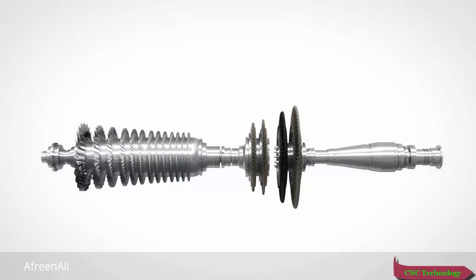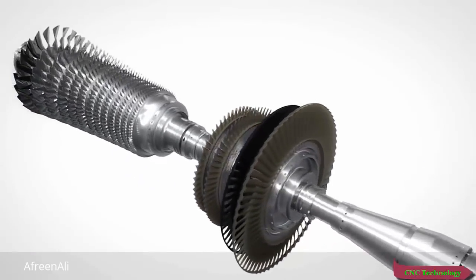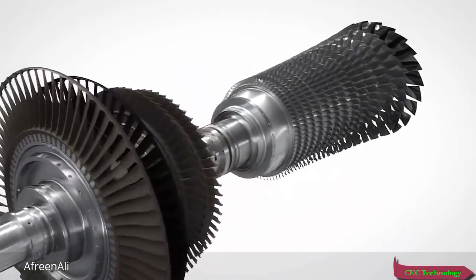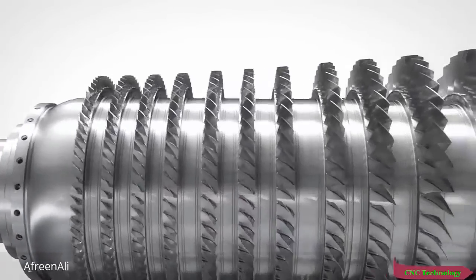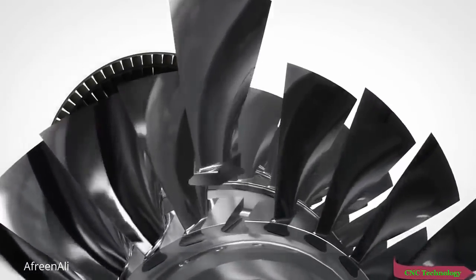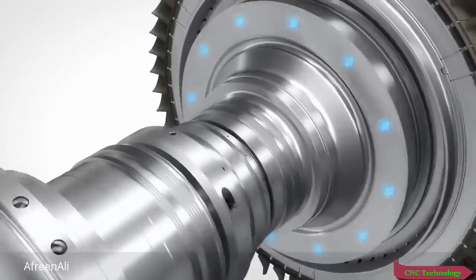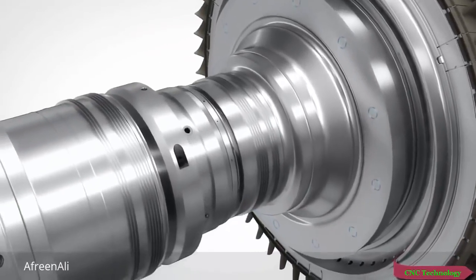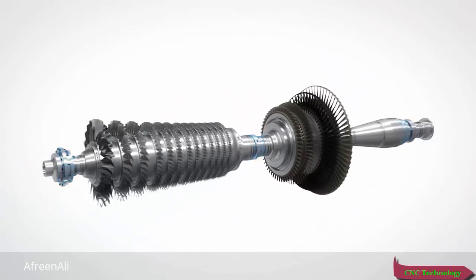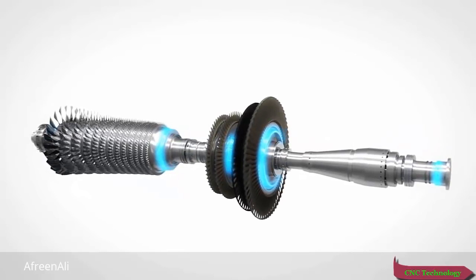The rotors incorporate the heritage of Siemens electron beam welding. The single rigid compressor rotor body ensures reliable, stable, and uniform run-up in hot or cold conditions. Axial blade attachment grooves allow blade replacement without rotor removal. The turbine discs are bolted to the compressor rotor and supported with mineral oil lubricated long life tilting pad bearings. The balancing planes allow field balancing on site without disassembly.